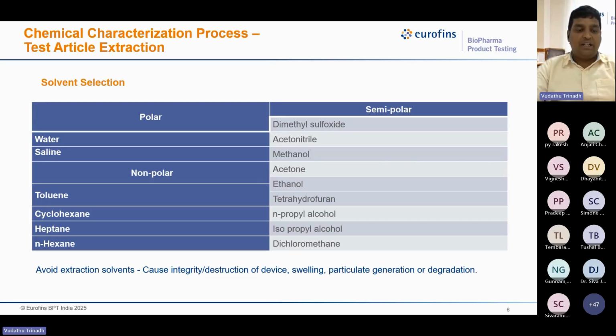It has to be kept in mind that while selecting these extraction solutions, before proceeding to the extraction, a development process should be done to check the compatibility of the solvent with respect to the medical device, to avoid degradation or loss of integrity of the medical device, swelling, or any particle generation. To avoid these things, a cross check should be done before initiation of extraction with respect to solvent and medical device. Based on the outcome, the proper solvent should be selected.